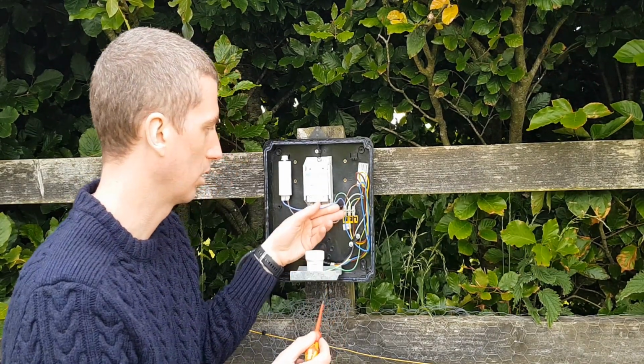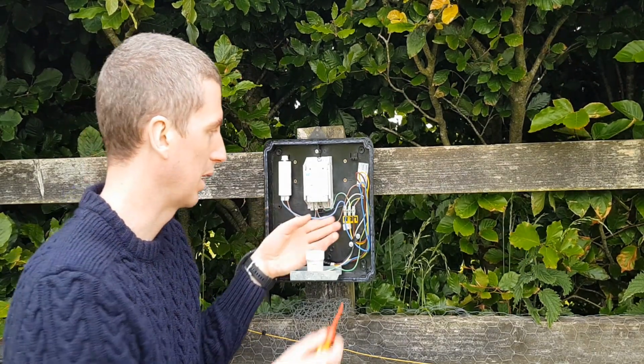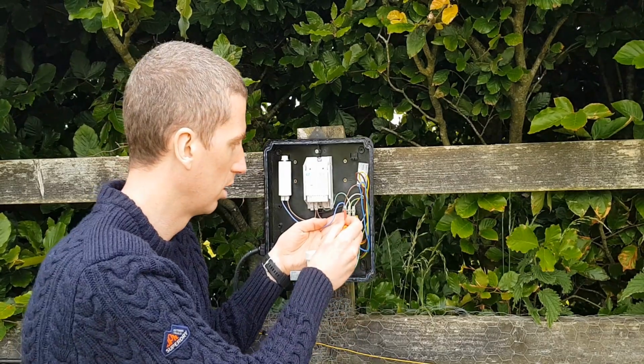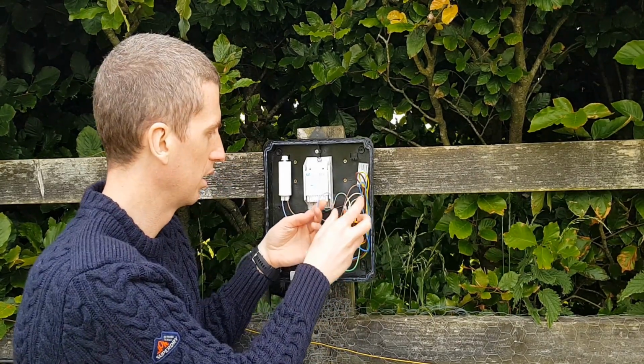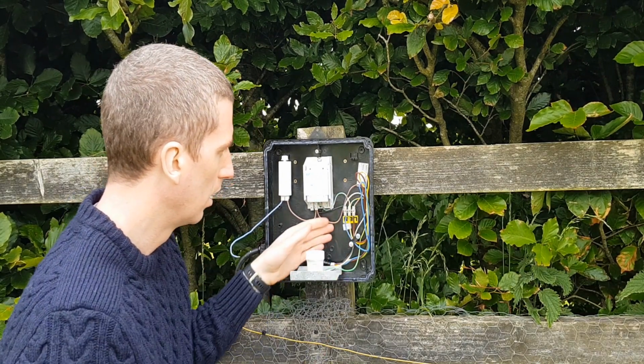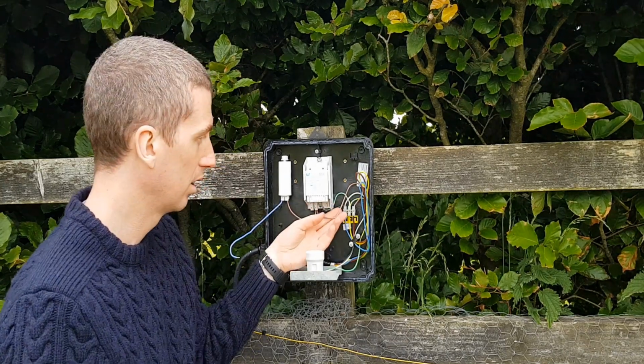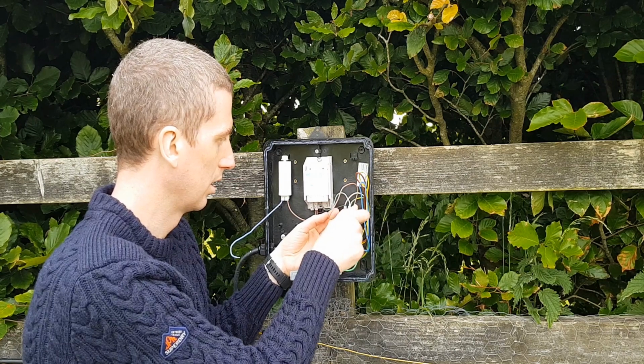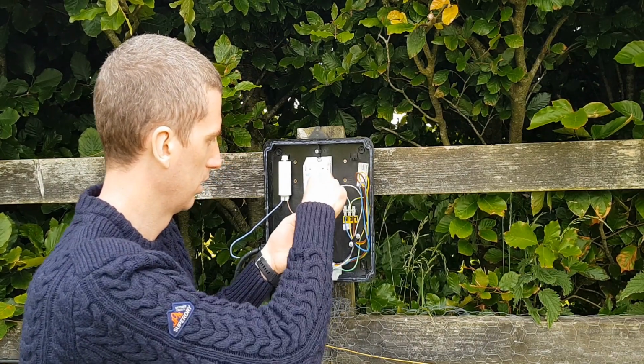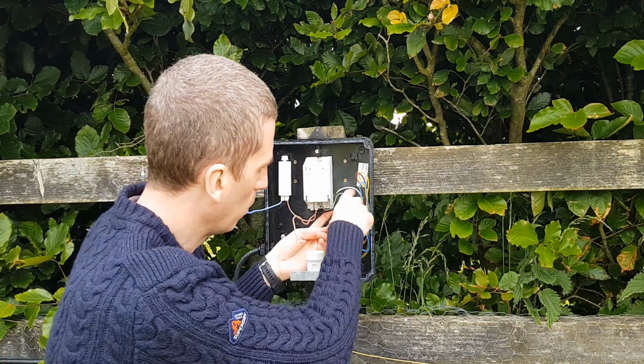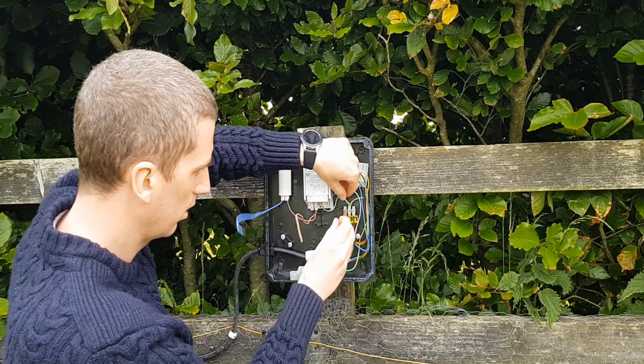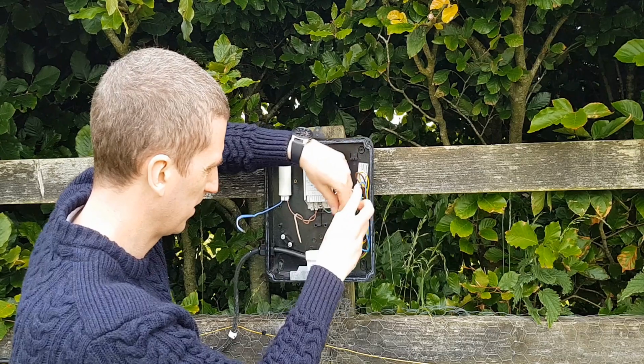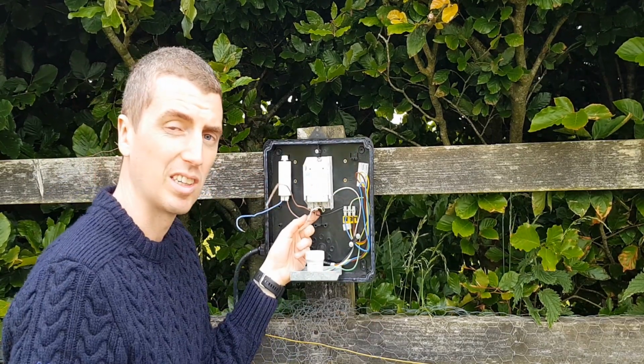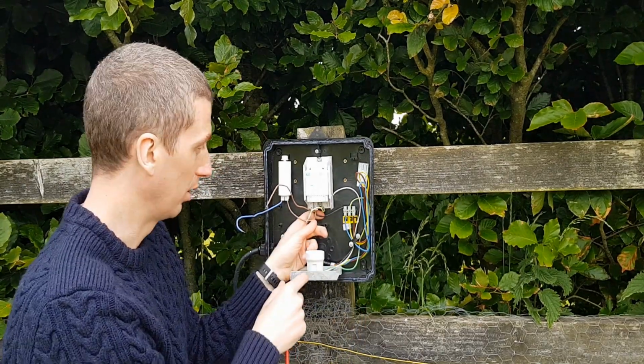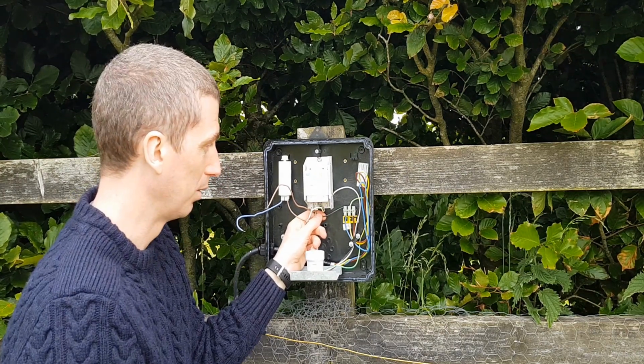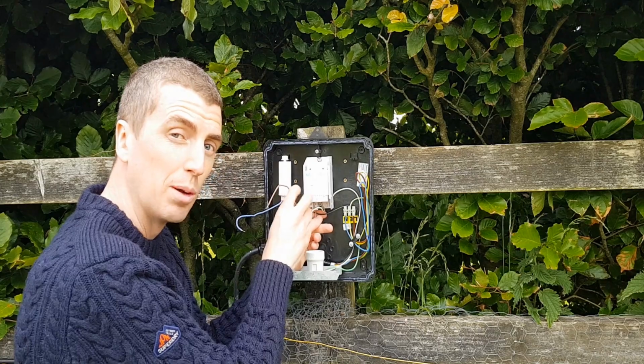So what I'm going to do now is disconnect the neutral cable going to the capacitor. To do that, I'm going to use my flathead screwdriver. I'm going to disconnect the blue cable. I'm then going to disconnect the ballast from the electrical supply terminals. So that's the ballast removed. And now I'm going to disconnect the earth. And the last cable I need to disconnect is the cable that's actually going to the light fitting, which is this black cable. This is the live cable, or phase cable, it's more commonly used.